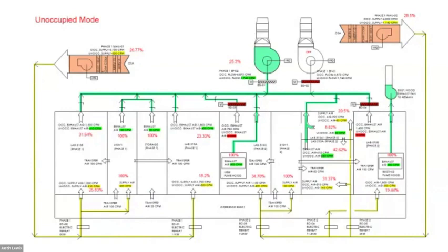We had multiple rooms that were supposed to maintain the same airflow in both scenarios, yet adjacent spaces, and even spaces that were connected to the same duct run, had dramatically disproportionate drops. We brought this up in an RFI. We had multiple meetings and went through this, and ultimately the unoccupied mode was abandoned, and we went with 100% occupancy because the unoccupied mode just wasn't practical for the system they were trying to install.